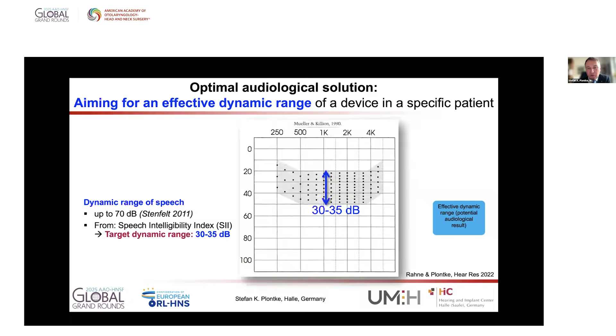And there are several factors influencing the effective dynamic range. So the maximum power force of an implant is reduced by the feedback. So we have to consider the feedback-free gain of a device. Then each device has a noise floor. That results in an intrinsic dynamic range of a device, which is definitely smaller than the maximum force the device can produce. Then, of course, the patient has a sensorineural hearing loss, usually at least. In active middle ear implants, we have a transfer deficit by coupling efficiencies or differences in coupling efficiencies. And since active middle ear implants involve a manipulation of the ossicular chain in the middle ear space, there's a possible bone conduction deterioration during surgery. For bone anchored hearing devices, at least in very asymmetric hearing thresholds and inner ear hearing thresholds, bone conduction thresholds, we have to consider impairment by contralateral routing of sound. And then over the years, we have a deterioration of bone conduction after surgery.